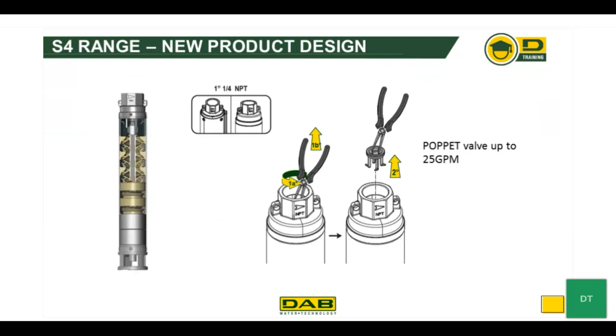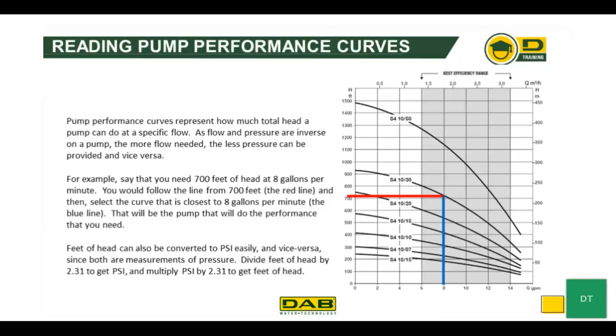The S4 range has a new product design in terms of the check valve or non-return valve. The poppet valve works up to 25 gallons per minute. Actually, it works up to the 25 gallon per minute range of the pump, and it can be easily removed if needed. Next, we're going to talk about reading pump performance curves. This is important in determining the right pump and motor combination for your submersible well.